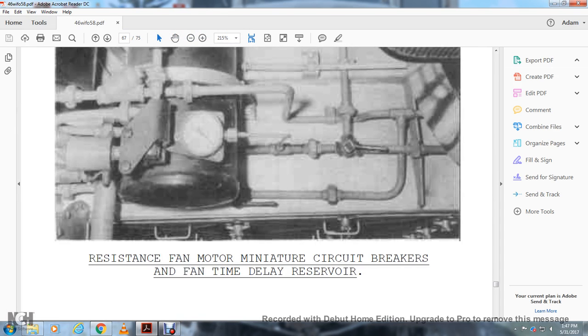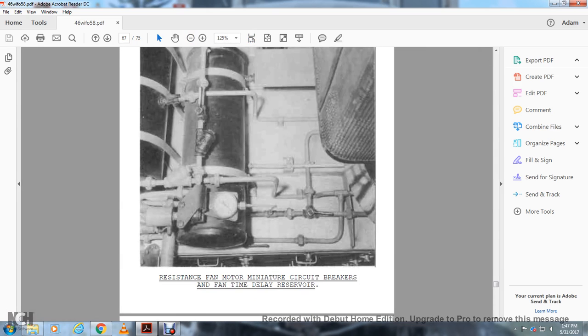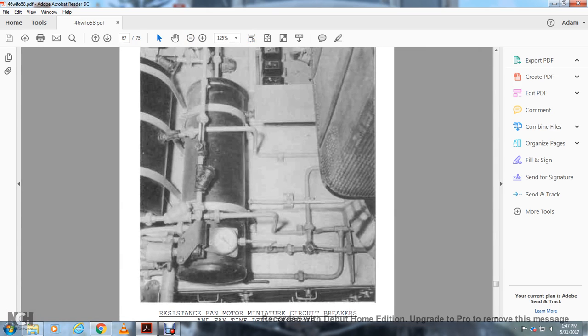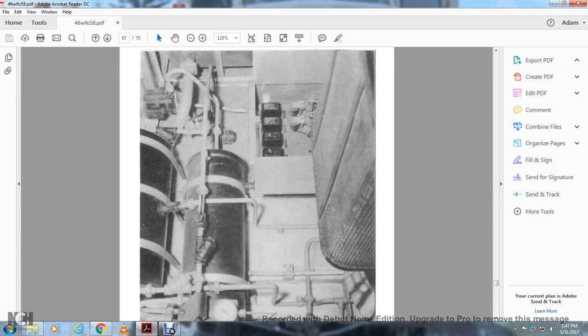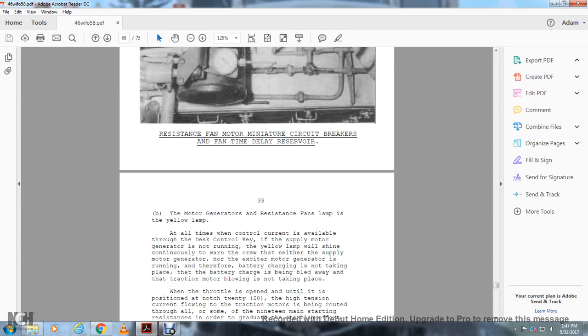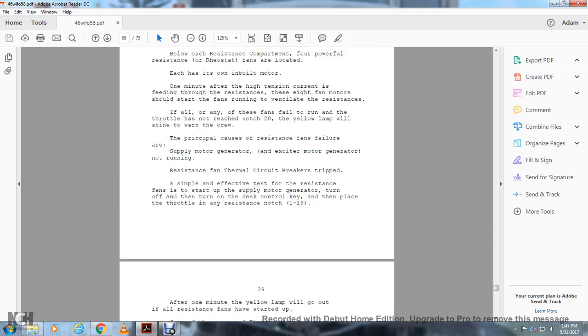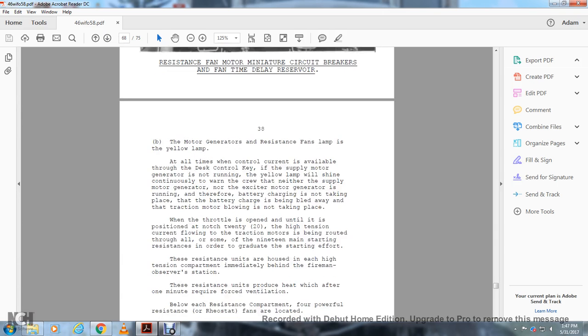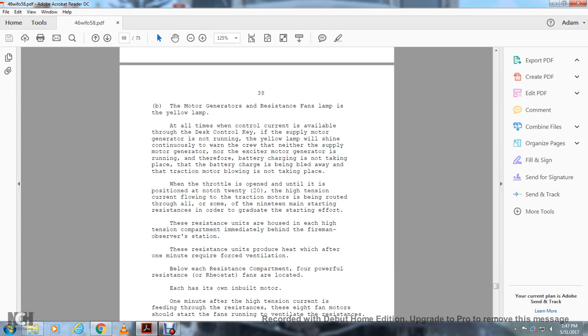Alright, let me back out of this. Resistance fan miniature circuit breaker, fan delays, time delay reservoir. Alright, the motor generator resistance fan lamp is yellow at all times. The control circuit is available through the desk control key. If the supply motor generator is not running, the yellow lamp will shine continuously, warning the crew that neither the supply motor generator nor the exciter motor generator is running. Therefore, the battery charging is not taking place. The battery charge is being bled away.